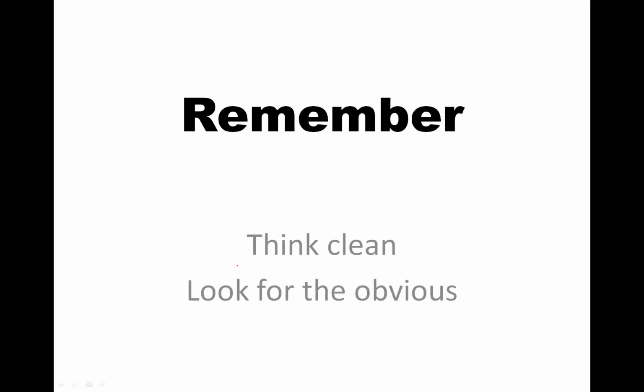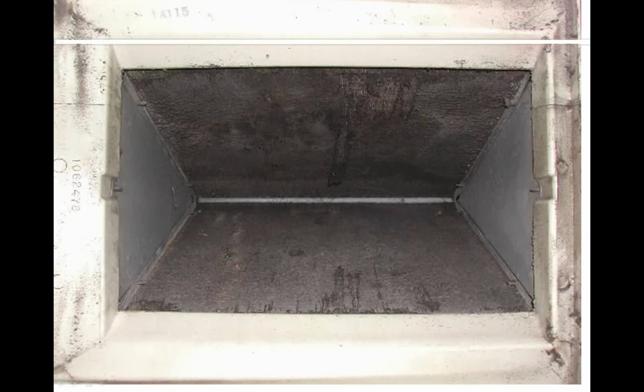You've got to remember when we're charging up a system, putting on your gauges is typically the last thing that we want to do. We don't want to just throw gauges on a system, because that doesn't tell us anything about the system performance if we have things like this, a completely plugged evaporator coil, right? The plugged evaporator coil is going to indicate low suction pressure, and that low suction pressure is going to throw us off. When I was younger and I first got in this industry, when I saw low suction pressure, the first thing I did was add gas because I wanted to get the suction pressure up. I didn't realize the impact airflow had on refrigerant pressures, and I didn't realize that a blocked evaporator coil would cause problems.